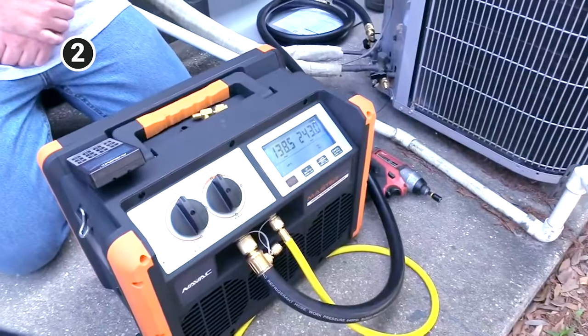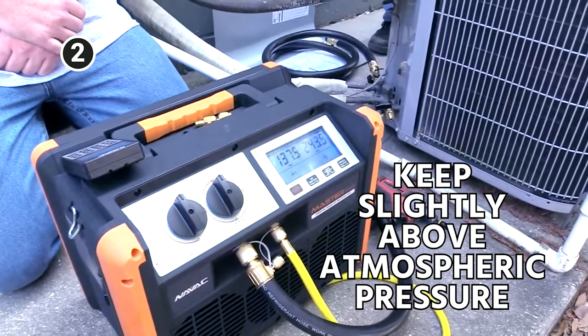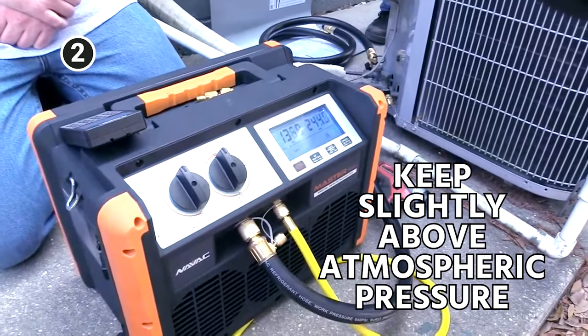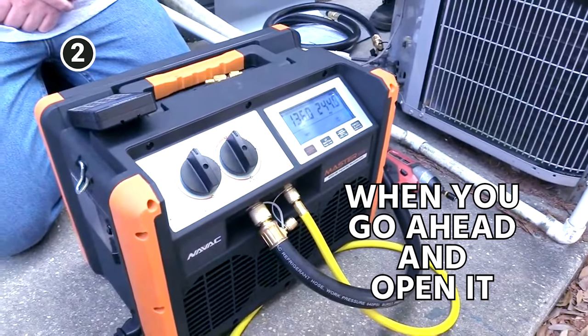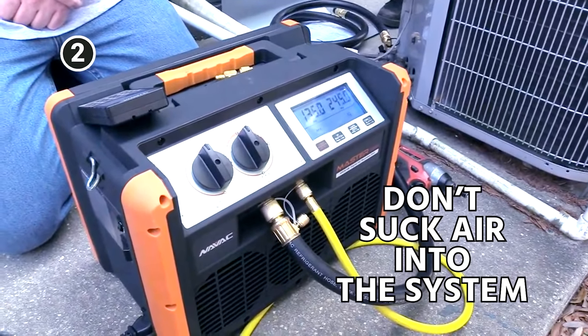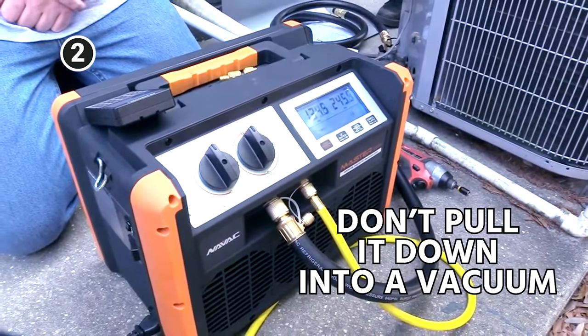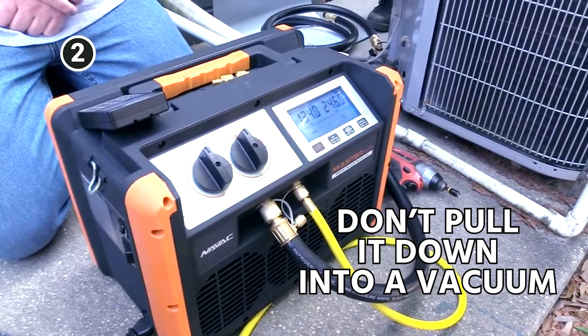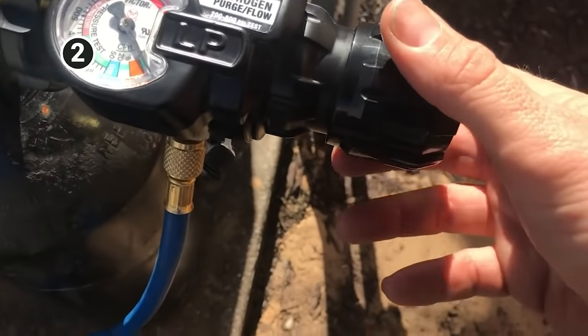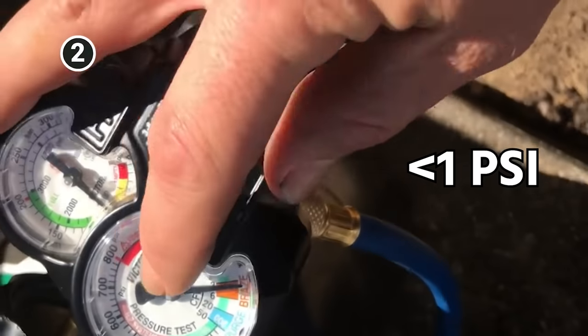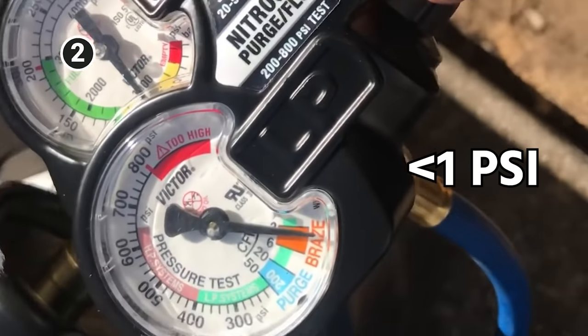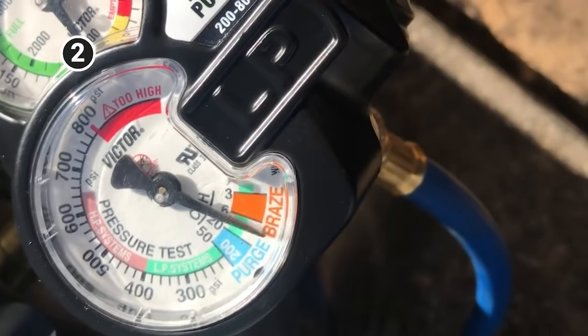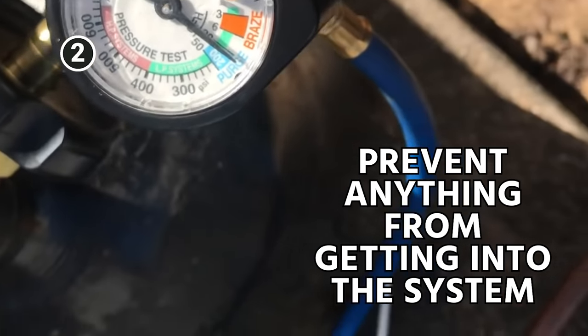Then go ahead and recover out that last little bit, but still keep just slightly above atmospheric pressure in the system when you go ahead and open it. You wouldn't want it to suck air into the system. So never pull it down into a vacuum when you're about to do a repair like this. It's actually a good idea once you get down to just under one PSI to go ahead and begin flowing nitrogen right at that stage. It's going to make your vacuums a lot easier and it's going to help prevent anything from getting into the system.